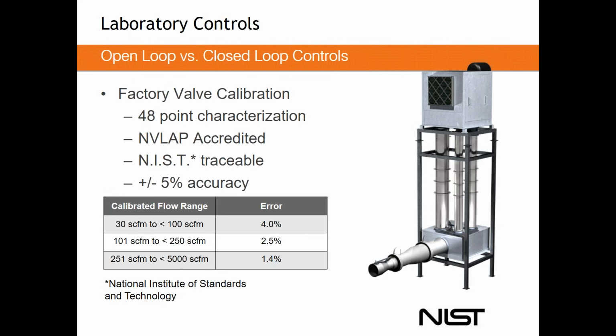At Antec, we have 3 of these rigs running full-time to do this kind of work, that are validated and accredited by the NVLAP organization, pardon me. So NVLAP is the National Voluntary Laboratory Accreditation Program. Basically, a third party has come into the factory and said the accuracies we claim to test to, and we claim for the valves, we are capable of actually producing in the laboratory. So what we have is a laboratory accredited by NVLAP, but not Venturi valves accredited by NVLAP. There's a bit of a misconception in the field that Venturi valves are NVLAP certified or accredited, where NVLAP doesn't accredit Venturi valves, they accredit laboratories that do this work.